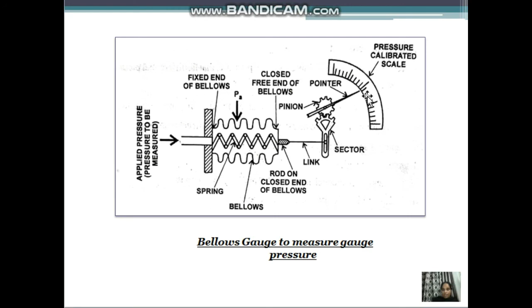Coming to the operation, the pressure to be measured is applied to the fixed open side of the bellows. Due to the applied pressure, the bellows expands lengthwise, causing a linear displacement of the rod at its closed free end. This linear displacement is proportional to the applied pressure. As the rod is connected to a link sector pinion arrangement, the linear displacement of the rod is magnified and converted to a rotary motion of the pinion. As the pinion rotates, it makes the pointer attached to it sweep over a scale calibrated to read pressure directly. As the pressure outside the bellows is normally atmospheric pressure and less than the applied pressure, the bellows gauge reads gauge pressure.